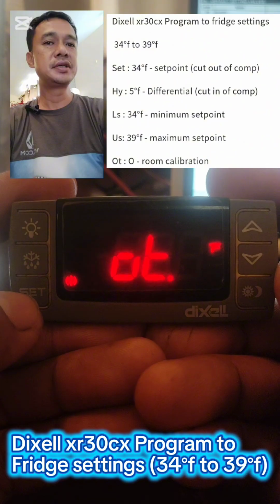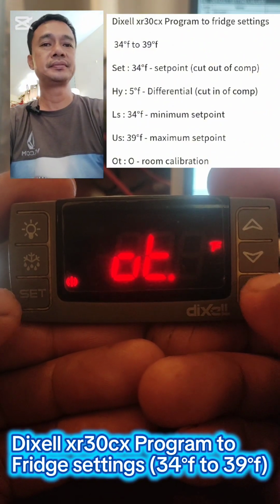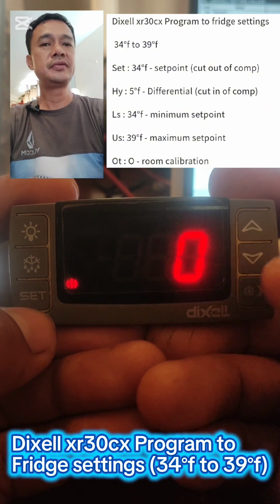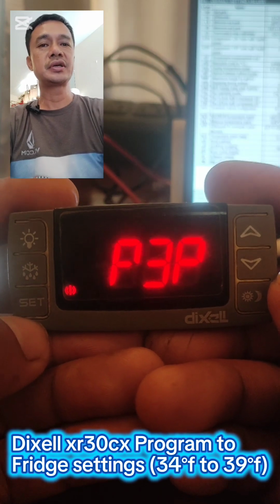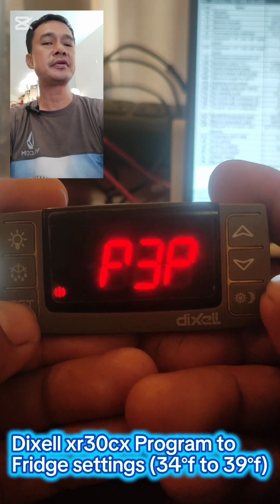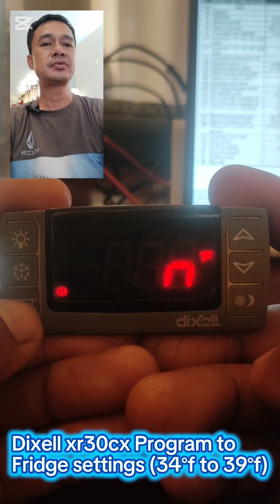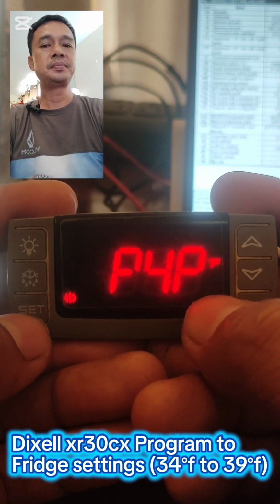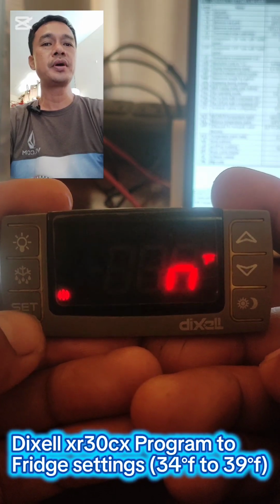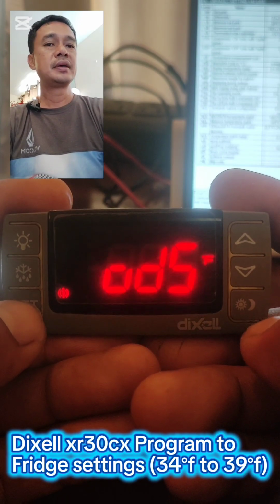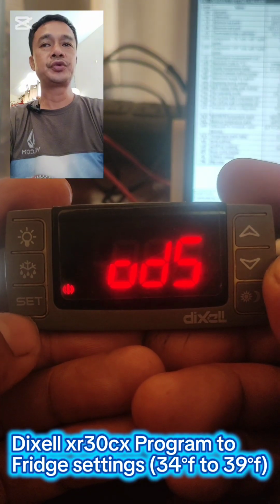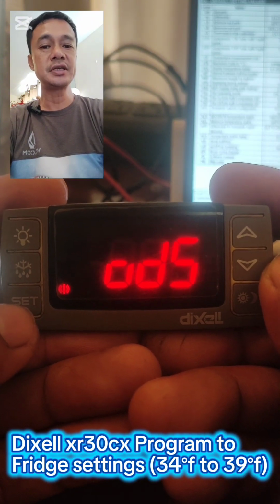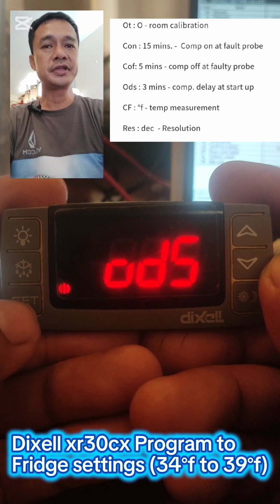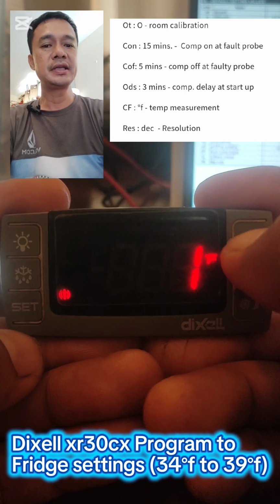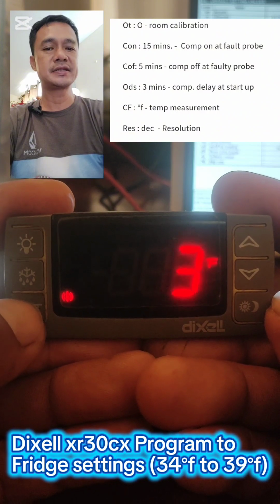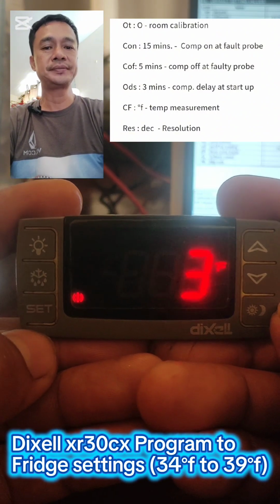And this OT is the room calibration. The default is 0. This is not our topic for today. P3P stands for third probe. It's set to no. And P4P stands for fourth probe, and it's set to no. And ODS, okay, we're going to program this ODS. This ODS is the compressor delay for the startup, and ideally it's set to 3 minutes.